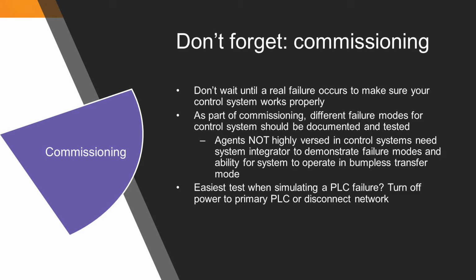They then observed the emergency generators come online, and in the process even failed the primary controller, so they could witness themselves that emergency power was provided to the load within the required time frame. Should the primary controls fail, they walked away confident they had a system that would provide ride-through capability from the generators and ultimately the UPSs, allowing the computing resources in that financial data center to continue operating.